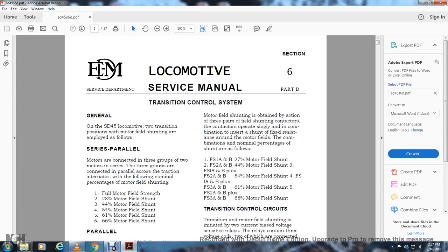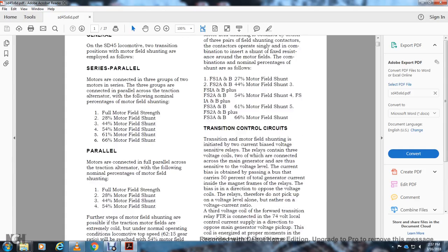Field shunt number 1A and B, 27% motor field shunt. Field shunt 2A and B, 44% motor field shunt 3. Field shunt 1A and 1B plus field shunt 2A and B, 54% motor field shunt 4. Field shunt 1A and 1B plus field shunt 3A and 3B, 61% motor field shunt 5. Field shunt 2A and B plus field shunt 3A and B, 66% motor field shunt.